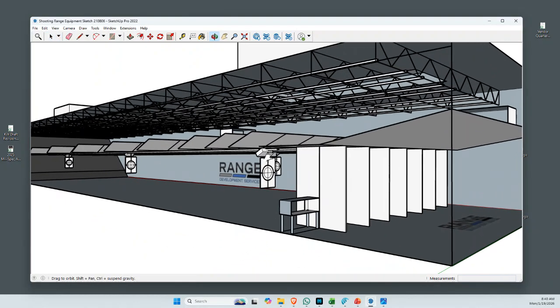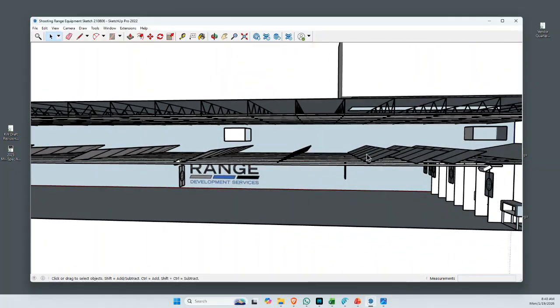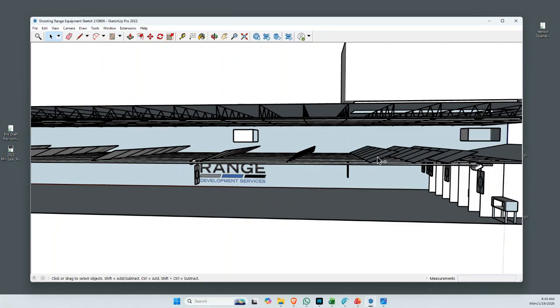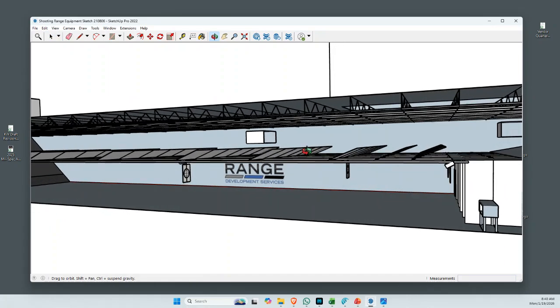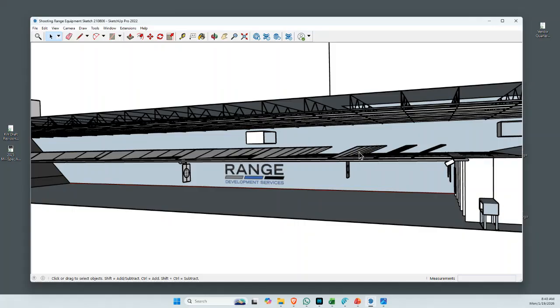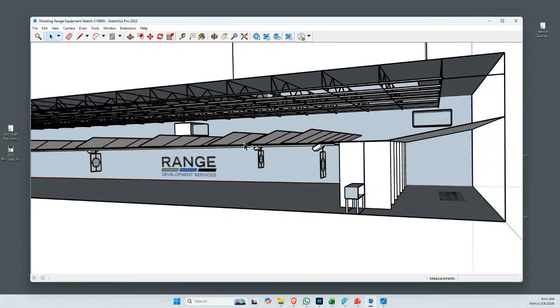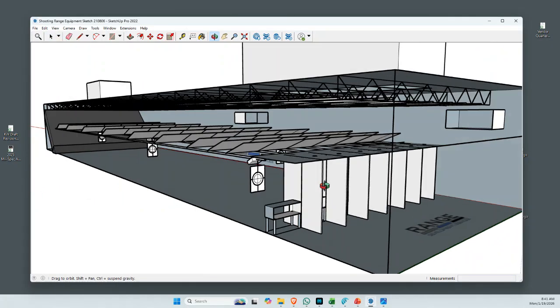The ballistic manufacturers do not supply downrange lighting that would need to be, in this case, mounted to the tops and backs of each row of baffles. So we'd have to get into, depending on the width of the bay, a calculation, a formula that I've got to determine the number of lights per row of baffles. Those lights will be the GC's responsibility to have the electrician provide the fixtures and the labor to install them. And of course, they need to be accounted for back all the way to the panel.